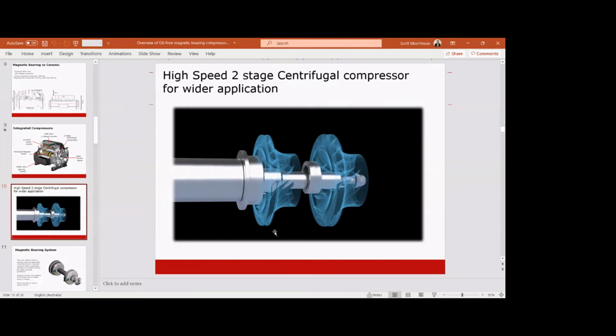So the maximum speed on these compressors is up to 45,000 RPM. There are manufacturers today working with technology of up to 200,000 RPM. But today in the market, the highest speed for a 300 kilowatt compressor is 45,000 RPM.